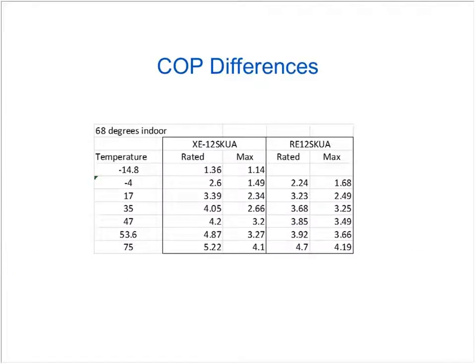Differences. So you're going to see two different systems here. Both are 12,000 BTU systems. And these are, of course, all Panasonic, because this is what I have the data for. But the XE is our top-rated model, and the RE is our lowest-rated model. And then you'll see a rated value and a max value. And almost all of your manufacturers, when you go to the service manuals, will give you the rated value and a max value. And the rated value is what they're going to give to AHRI, and we're going to talk about AHRI in a second.